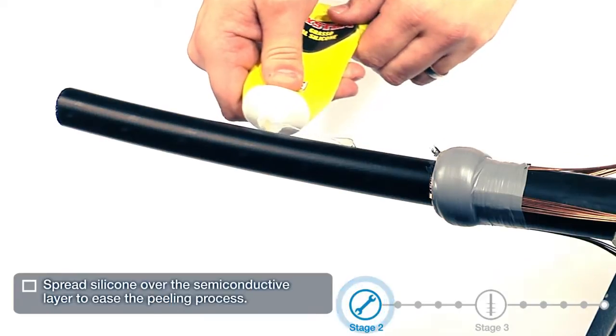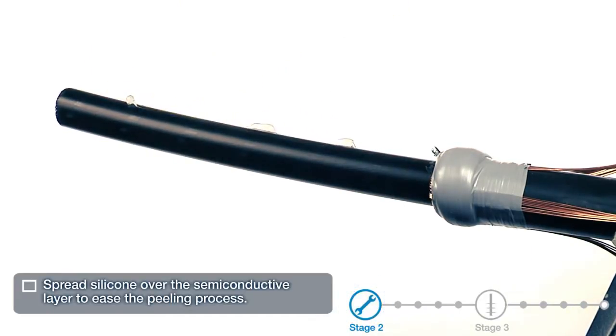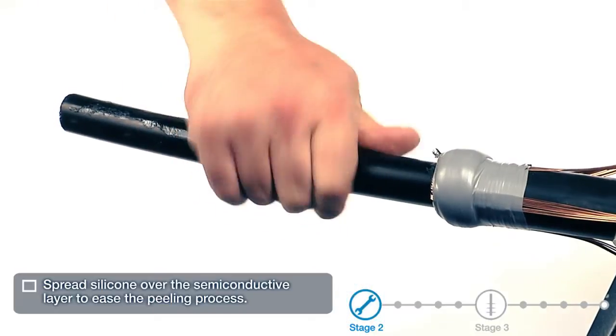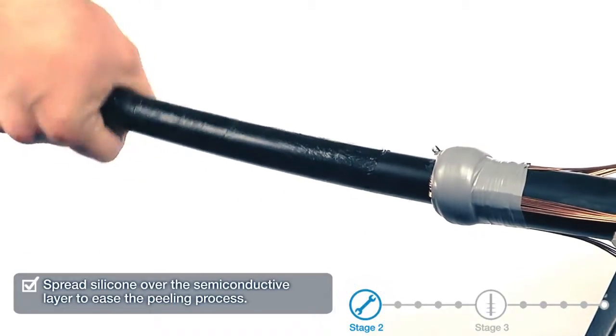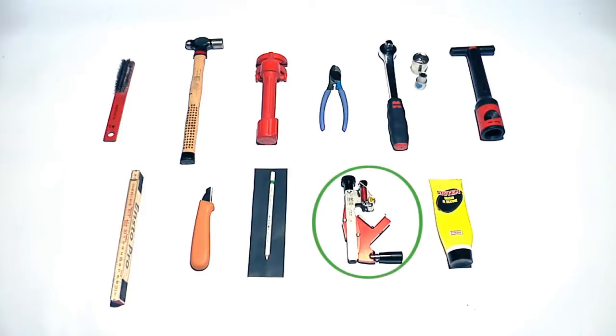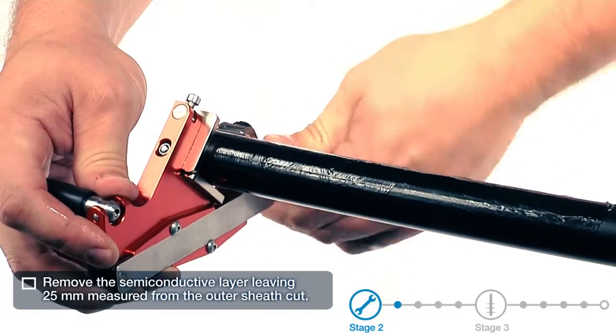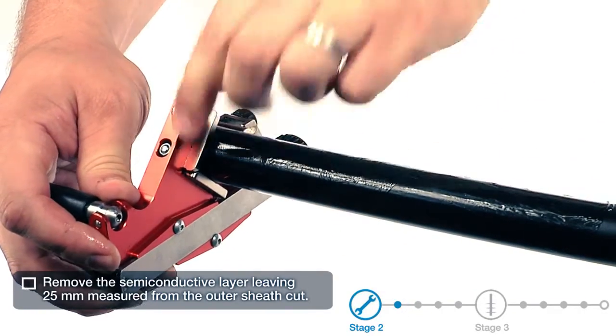Spread silicone over the semi-conductive layer to ease the peeling process. Remove the semi-conductive layer leaving 25mm, measured from the outer sheath cut.